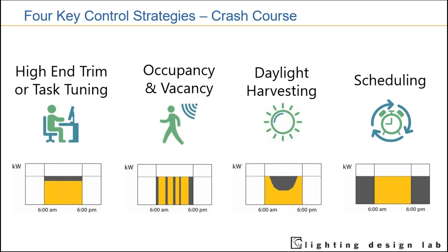Then, scheduling is another great key control strategy, where you can program by time of day or by following sunrise or sunset. That's called the astronomic time clock. You may want different zones of lighting to go on or off, or dim, or do something different. Scheduling also gets a little fancier when you can control sensors as well. So, during school hours, I want my sensors to turn lights on to a bright level, but not off. I want them to go to a 20 to 25% background level for safety. But outside of school hours, I want those sensors, whenever they don't detect anyone, to have the lights go off.